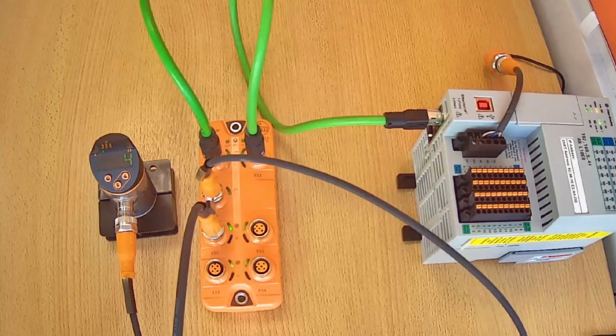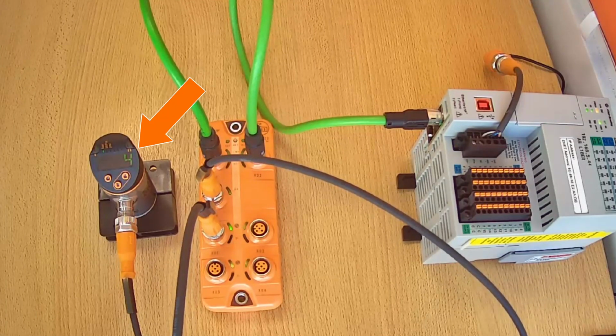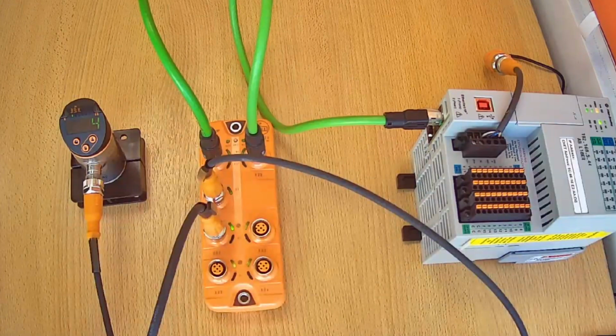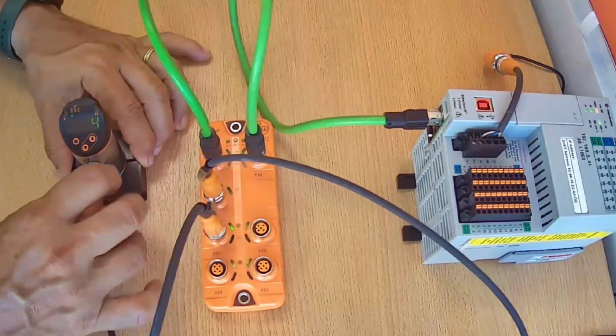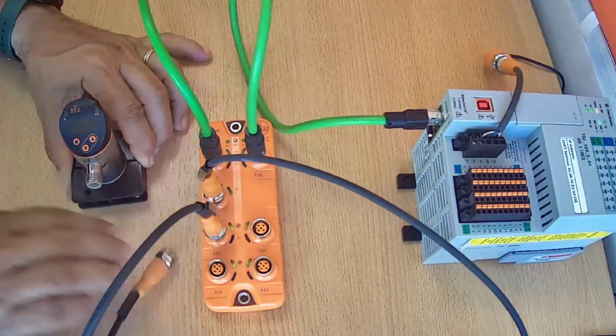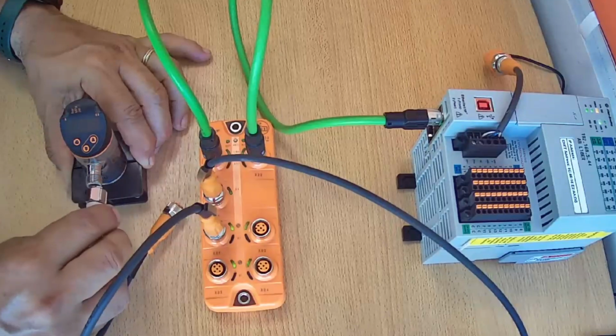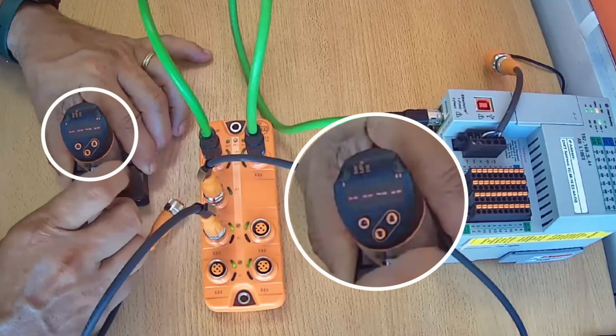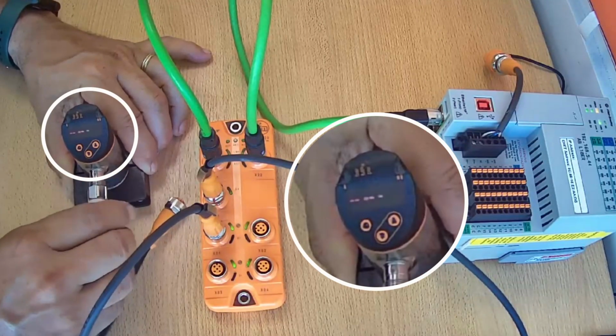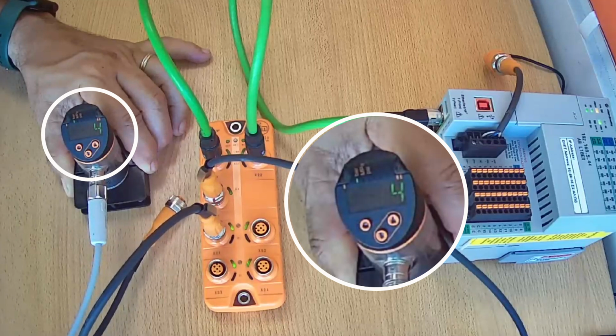Let's now move on to the data storage function. As you can see, the current pressure value is displayed in green. This parameter set with a green display is stored in the IO link master due to the backup and restore function. We will now simulate a new pressure sensor with factory settings. To do this, we connect the existing sensor to a power supply without any connection to the IO link master or the controller and set the factory settings manually.